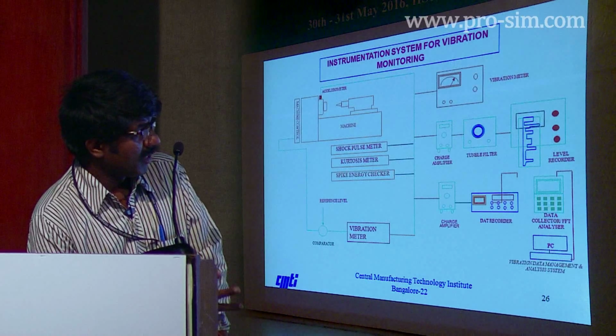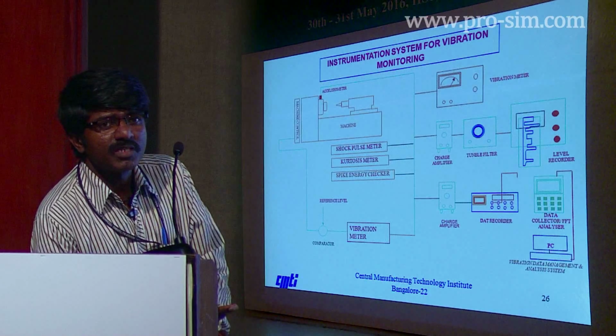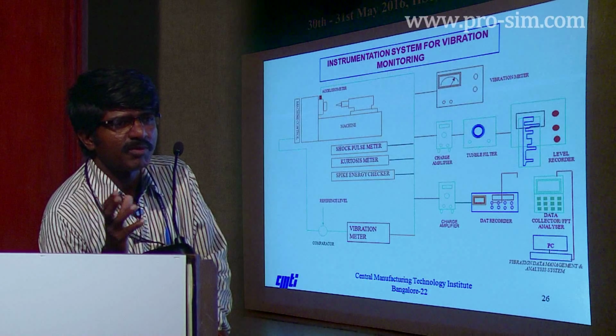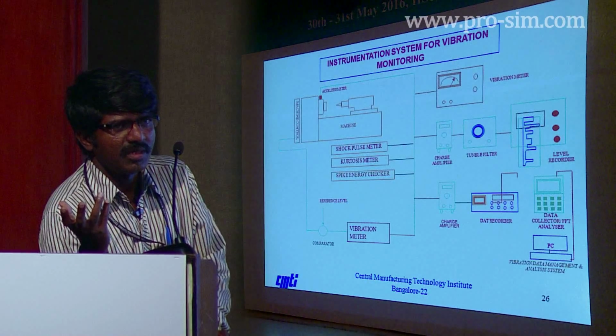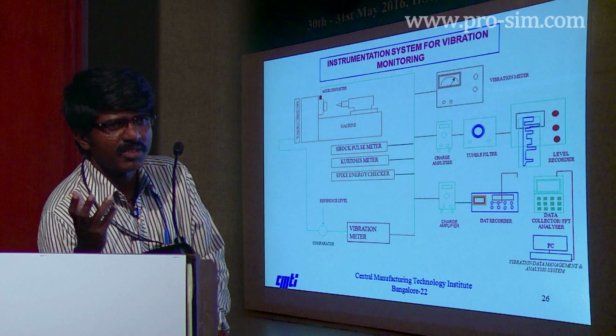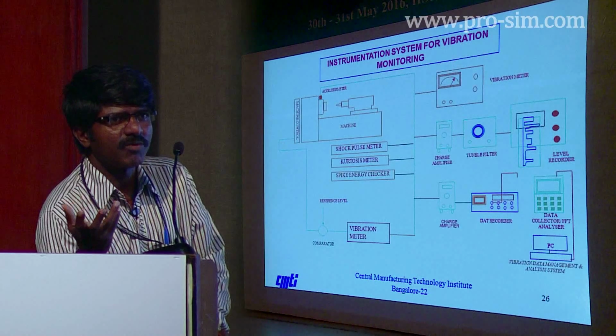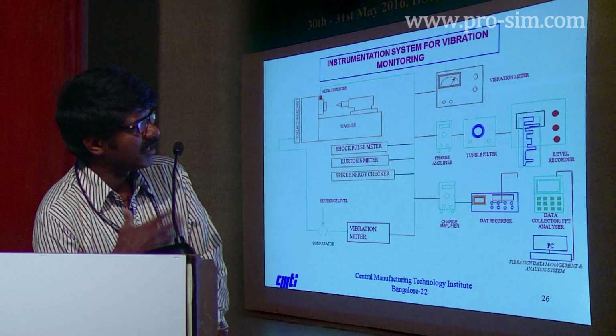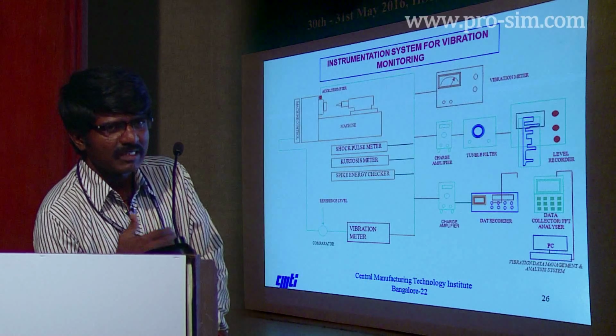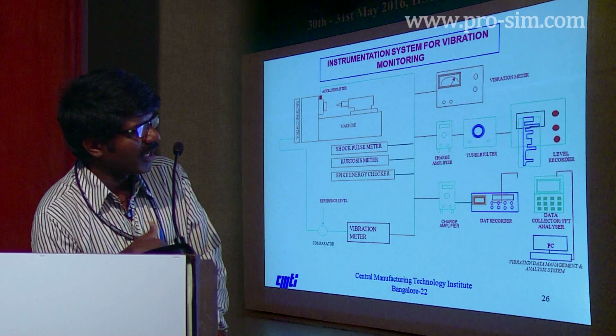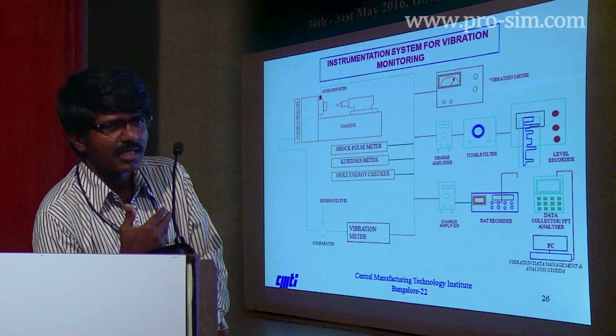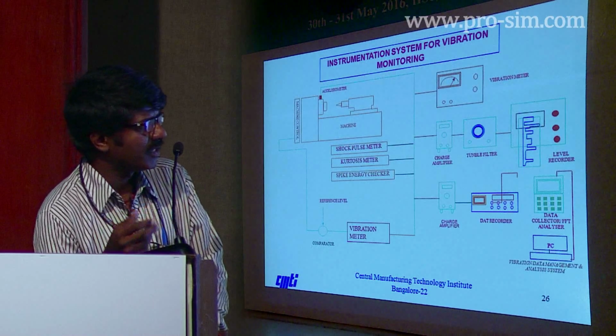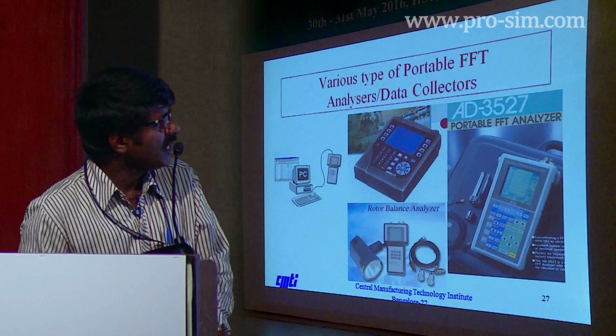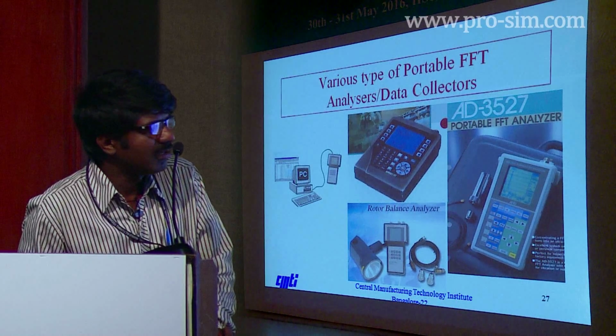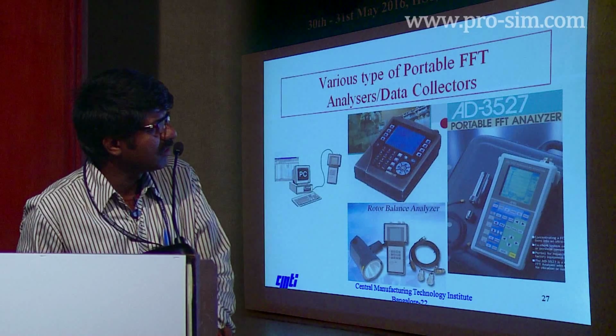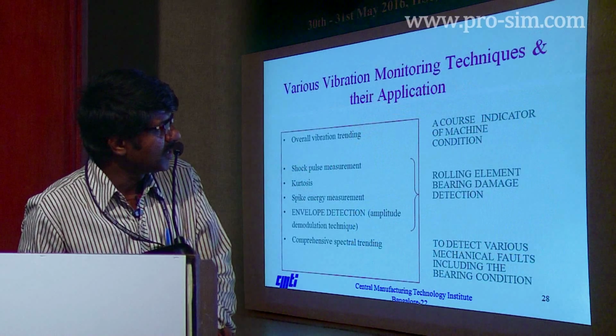Earlier, our people were using only a vibration meter. It gives only the overall vibration level. From that, we cannot conclude what is the problem in the machine. Say 5 millimeter per second of vibration we have measured; we don't know what reasons it is because of. So next came the level recorder and other things. Afterwards, things advanced, and now we are using FFT analyzers and PC-based data management systems. Different analyzers are available in the market for vibration data collection and measurement.